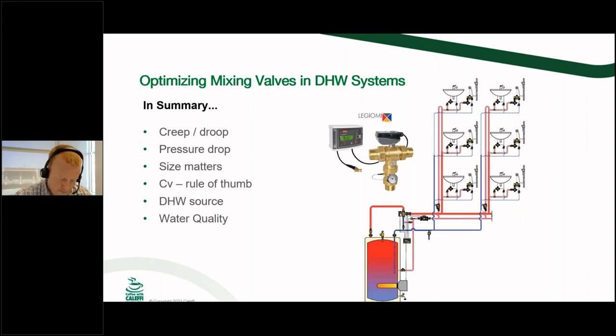Okay, and then I've got another one. Let's say you've got a large hot and cold pressure differential, and you're using a mixing valve with check valves. Is there a scenario where you could have flow through where the cold water would flow into the hot water system? Well, if you've got check valves at the inlets of the mixing valve, and that's a good point too.